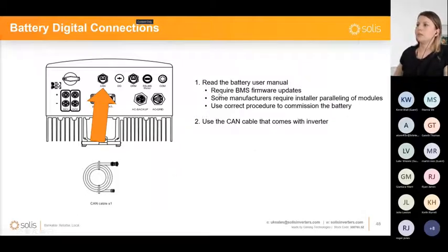The batteries, well, normally you only have to connect the CAN communication cable from the battery to the inverter. The battery management systems on the list have been tested to work with our inverters. So if you're just selecting the correct type of battery, then it should work smoothly. But if you do have some problems with communication, you can get in touch with us, but you can also get in touch with the battery manufacturers, because sometimes even if you find the battery in our list, it might be that that battery has an older firmware and it might need a firmware update. That's very rare, but I'm just mentioning it.